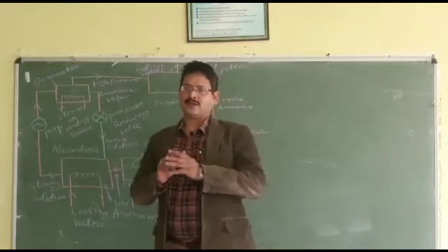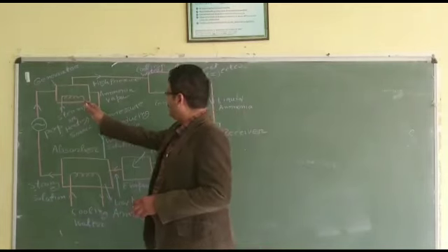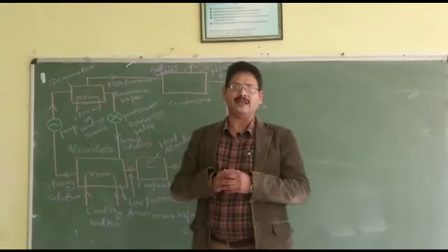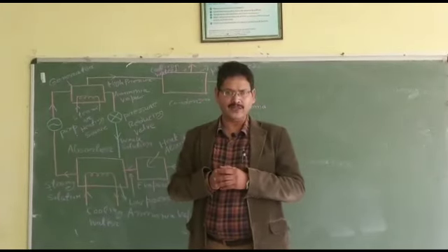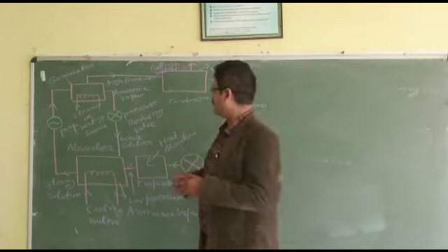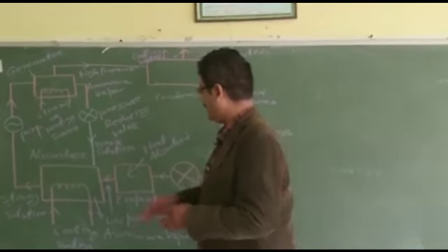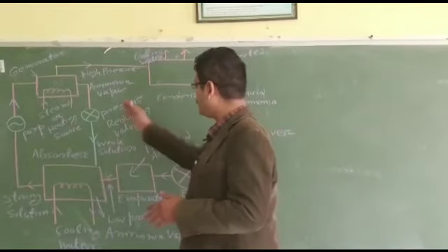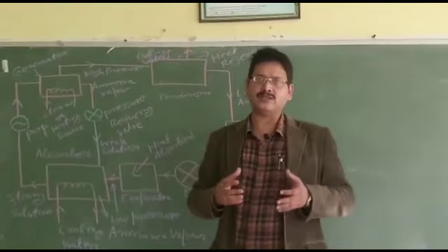So, after the ammonia leaves the generator, some weak solution of aqua ammonia, that is containing less ammonia and more water, is left in the generator, and that returns to the absorber after passing through the pressure reducing valve, which reduces its pressure.